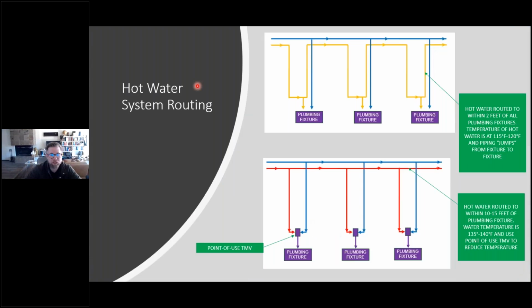Our hot water routing also has an impact. Keep in mind, our pressure drop is based off of a velocity and a given pressure drop per 100 lineal feet of pipe. So if you're using jump routing and going up and down fixtures, kind of like a purified water system, which is certainly one approach and one that was mentioned in that design guide as an option, that's going to increase your length. So you're going to have a greater pressure drop.